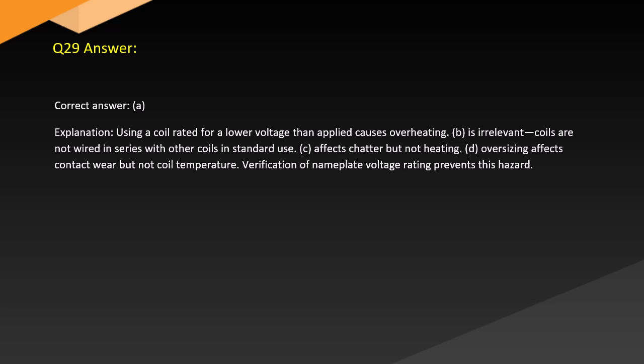Answer. Correct answer: A. Explanation. Using a coil rated for a lower voltage than applied causes overheating. B. Is irrelevant. Coils are not wired in series with other coils in standard use. C. Affects chatter but not heating. D. Oversizing affects contact wear but not coil temperature. Verification of nameplate voltage rating prevents this hazard.